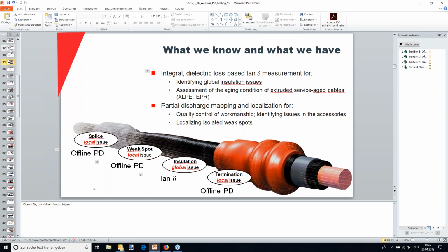Well, see, this is a bit of a problem because all the test standards, especially the cable test standards, want the cable to be isolated from anything else. So you do have to take off the terminations from the cable.